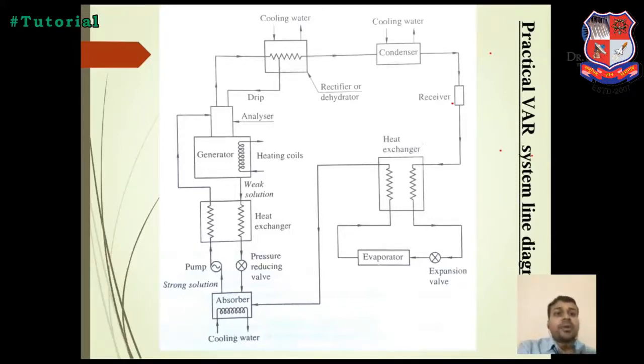Then the refrigerant passes into the absorber, and the generator passes weak solution. There are two words here, weak solution and strong solution. Weak solution means there is a higher H2O content compared to NH3, and strong solution has a much higher NH3 content compared to H2O. The weak solution is passed through the heat exchanger to the pressure reducing valve and the absorber. The absorber mixes the H2O and NH3 coming from the evaporator, and it creates a strong solution.